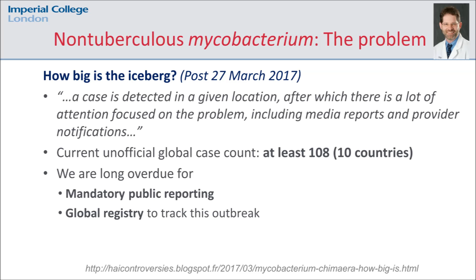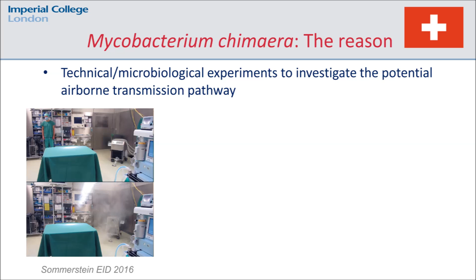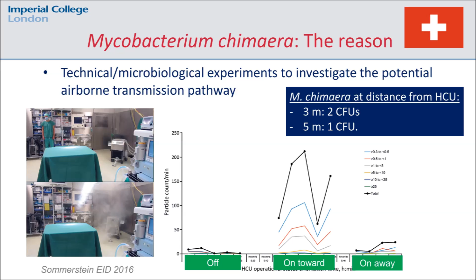This study is an experimental study. The authors put a 3T unit in an operating room and looked with a smoke test at where the smoke was going when the unit was on. They saw that once the HCU was off, there were no particles. When it was rotated towards the table, there was an increase of particles on the table, and when it was rotated away, the particle count decreased. It means that rotating the unit can have an impact. The orientation of the unit can have an impact on the potential contamination during surgeries. And it was also true with distances from 3 meters to 5 meters.